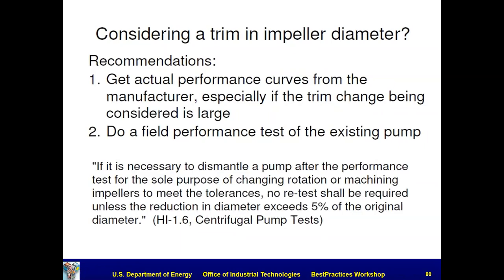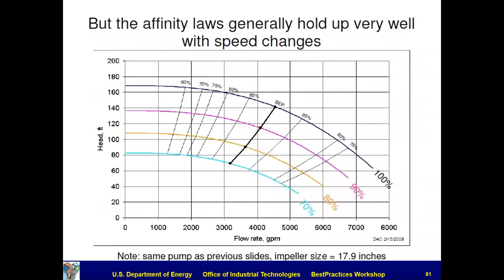Consider trimming and impeller diameter recommendations. Get actual performance curves from the manufacturer, especially if the trim change being considered is large. Do a field performance test of the existing pump. And there's some stuff from the Hydraulic Institute that I'm not going to read over. Okay, but affinity laws generally hold up very well with speed changes.